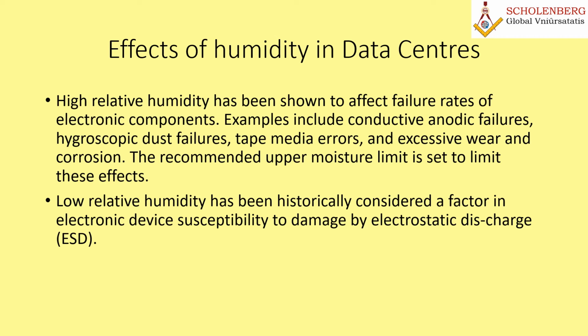Everyone is going to ask you this question: why are you going for such a low humidity range? Why is 8% the range? Why not 30% for static charge? You can always tell your client that lower humidity is not a concern here for data centers. Lower RH is not at all affecting the machines. Higher RH, yes, affects them, but lower RH is not a concern, for the simple reason that a recent study has shown that lower RH is not a concern, and the overall humidity can be monitored by dew point, the moisture content in the air, rather than relative humidity. The dew point is the correct measure because it's constant throughout.